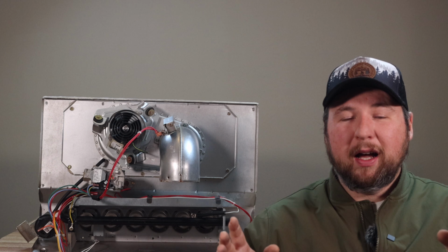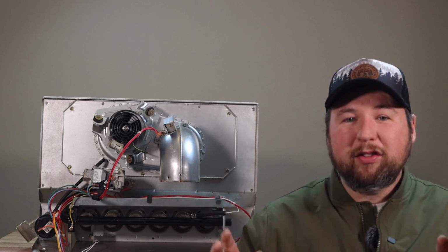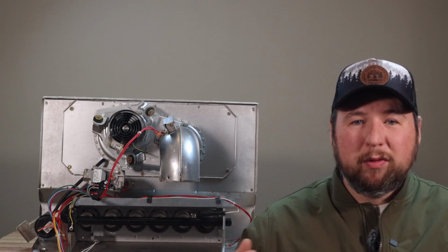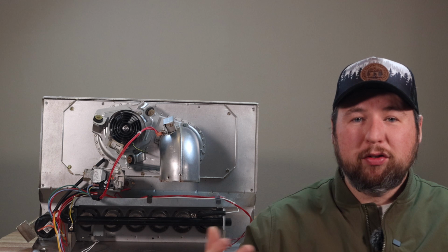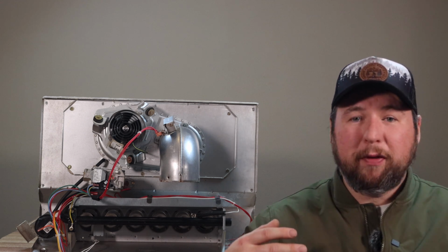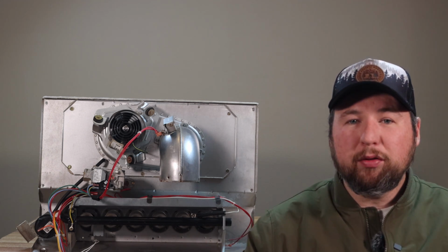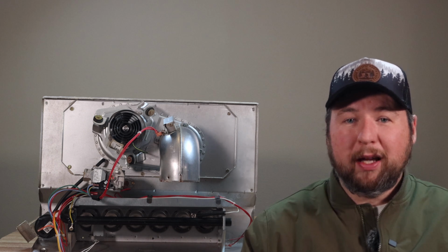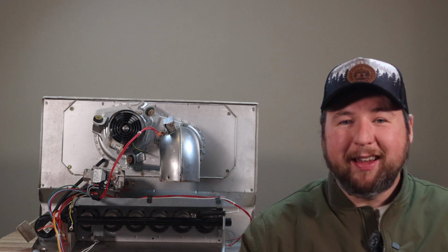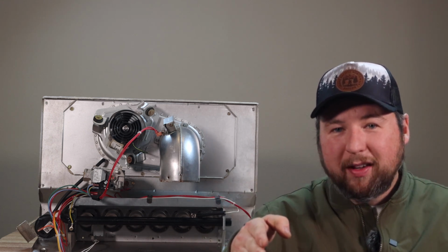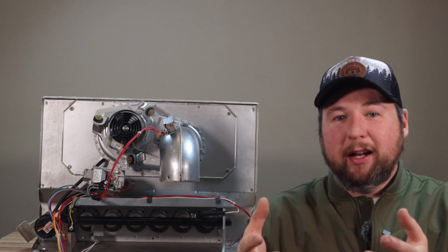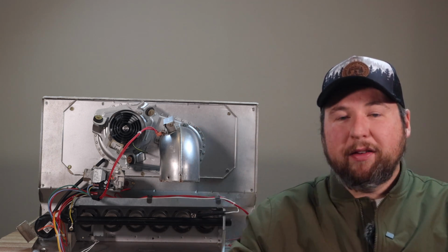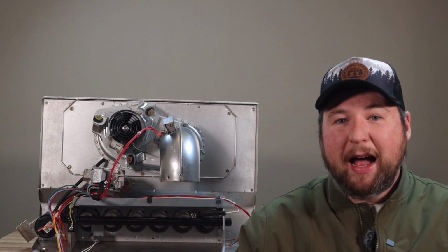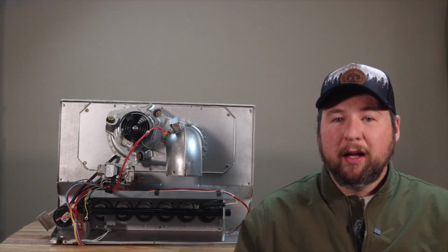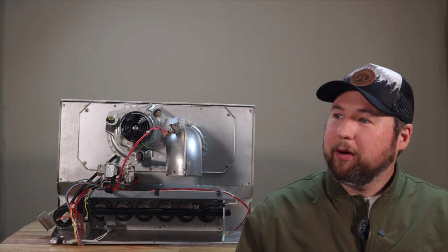There are different types of heat exchangers. There's the original style, which was off of a natural draft furnace. It didn't have an inducer. Basically, it was literally a campfire in a metal box. So basically you have barbecue burners in there, and it would light up, and the heat would just rise naturally. That's why it's called natural draft, because it creates a natural draft. I'm going to show you a chart of how one of those work.